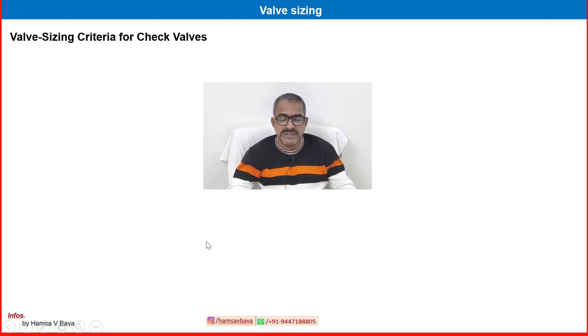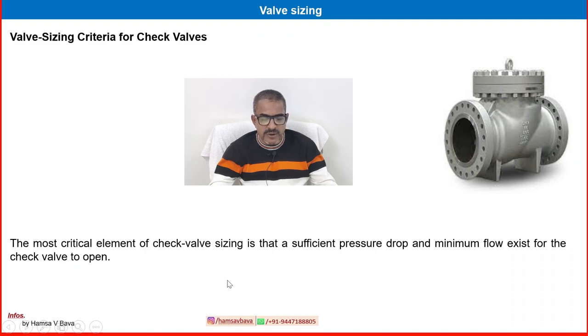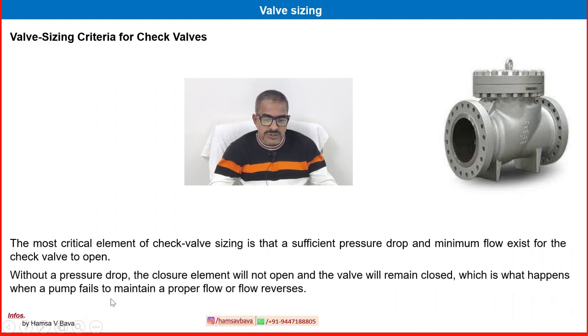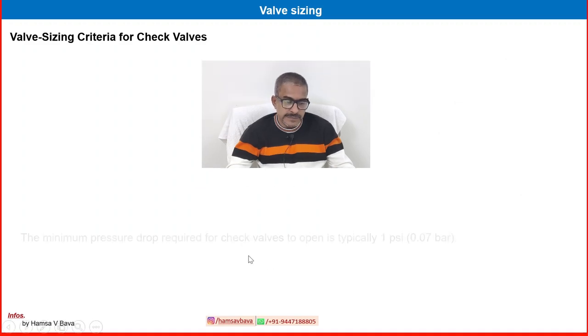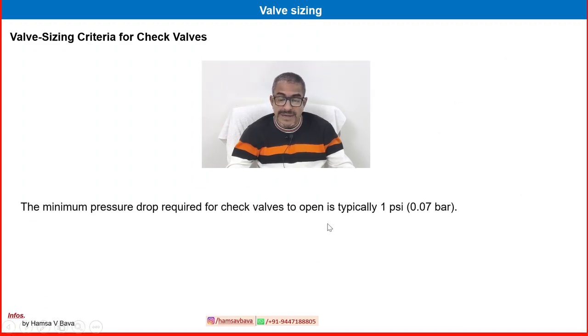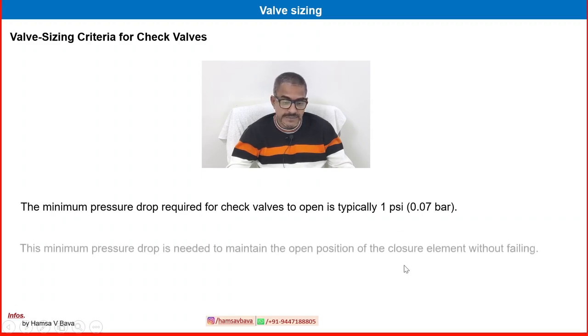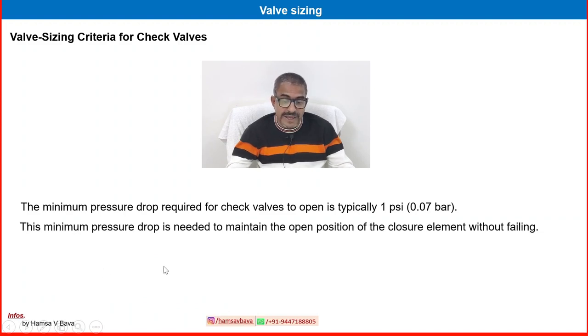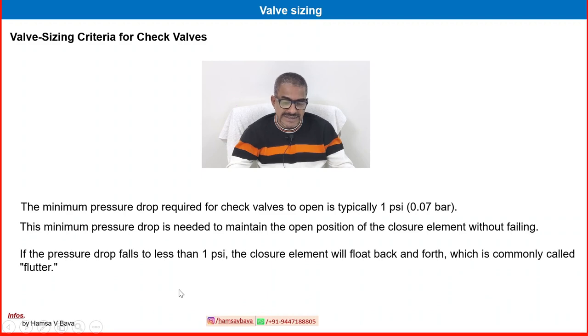Valve sizing criteria for check valves: the most critical element is that a sufficient pressure drop and minimum flow exist for the check valve to open. Without adequate pressure drop, the closure element will not open and the valve will remain closed, which is what happens when a pump fails to maintain proper flow. The minimum pressure drop required for a check valve is typically 1 psi or 0.07 bar, needed to maintain the open position of the closure element. If pressure drop falls below 1 psi, the closure element will float back and forth — commonly called flutter.